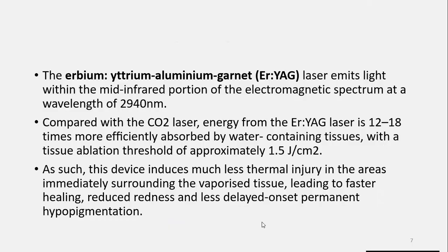Then about the erbium YAG lasers. The erbium, yttrium, aluminium, garnet lasers emit light within the mid-infrared portion of the electromagnetic spectrum at a wavelength of 2940 nanometers.